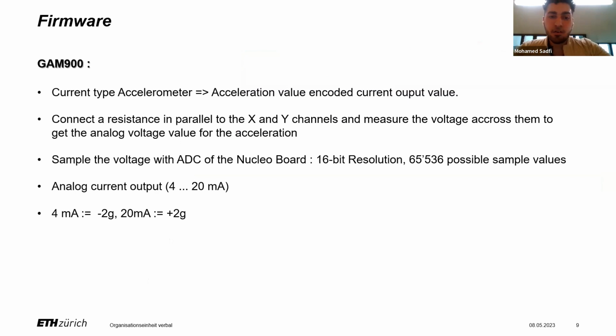For the GAM 900 sensor, an accelerometer, it's a current type sensor. To read the acceleration, I had to connect a resistance in parallel to the channels and then measure with the ADC the voltage across the resistance, because the ADC only takes voltage inputs. The ADC of the board has 16-bit resolution, so it can measure up to 65,536 possible sample values, which is pretty accurate. The sensor itself sends an analog current output between 4 and 20 milliamps, where 4 milliamps is the minimal acceleration, minus 2 Gs, and 20 milliamps is the maximal acceleration.